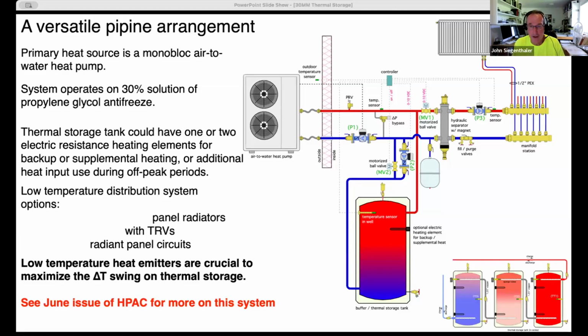But you also see the tank down at the bottom. At times when the cost of electricity is low, and typically these are night times or weekends or major holidays when the load on the utility grids is low, what we would do is close a valve just to the upper left of that hydraulic separator. It's labeled MV1. And the circulator that pumps the fluid through the heat pump would send that heated fluid down into the top of that thermal storage tank. Cool water would come out the bottom. You'll see another valve labeled MV2. That valve would open. So that's the flow path between the heat pump and thermal storage. We'd call that the charging mode.